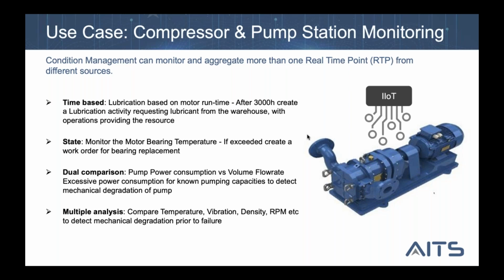Sometimes it might be time-based data. So after 3,000 hours, I want to create a certain work request, a state based on certain event or alarm. If a temperature, motor bearing temperature, exceeds a certain threshold, let me do a work order, or a comparison between two different data points, pump power consumption versus volume flow rate, which might not be matching. There might be way beyond what the theoretical value should be. I can match them, and accordingly, from the analysis in the SCADA system, create a work request in the maintenance system, and multiple other analyses. Most importantly, connect and collect, historize the proper data, and then use it and extend it.